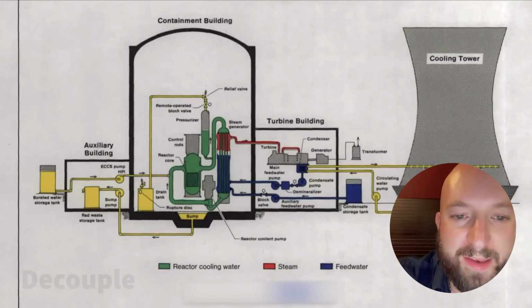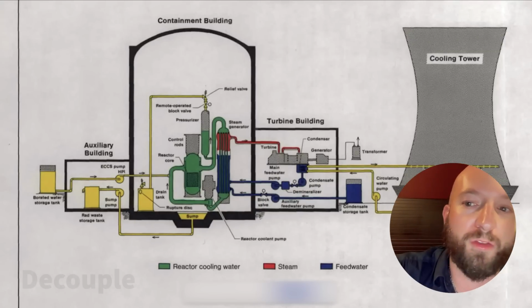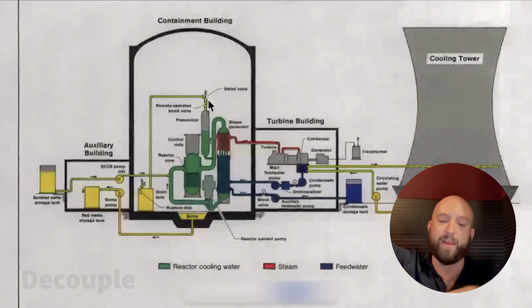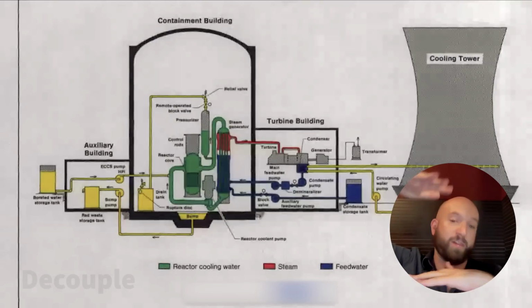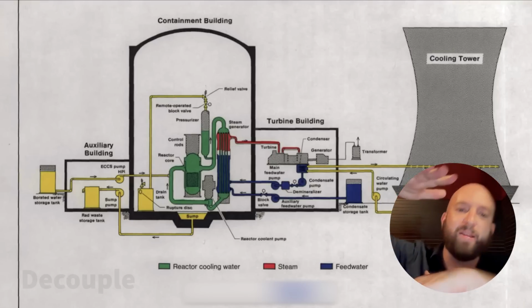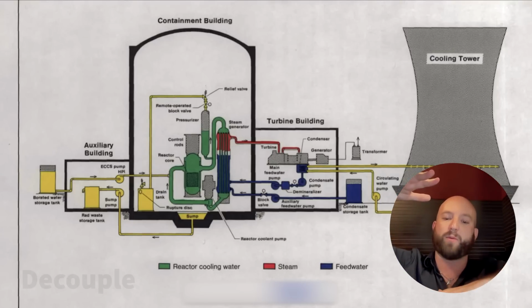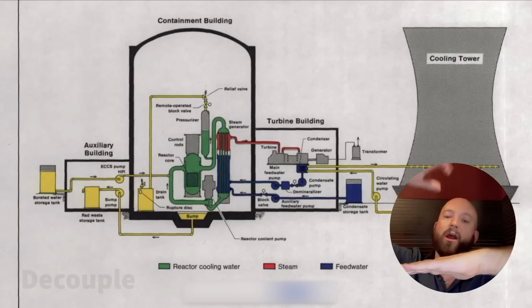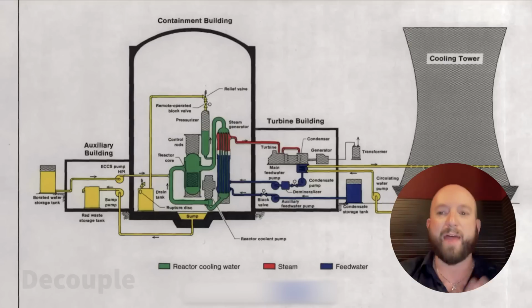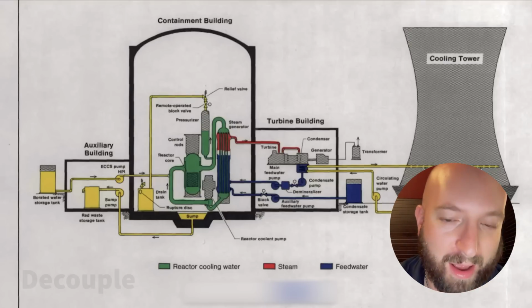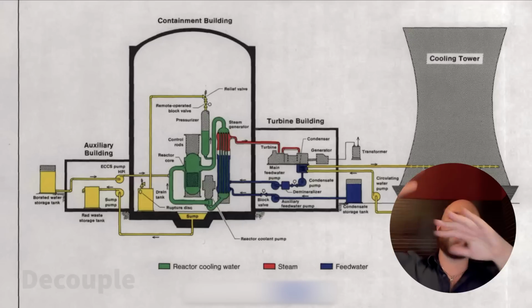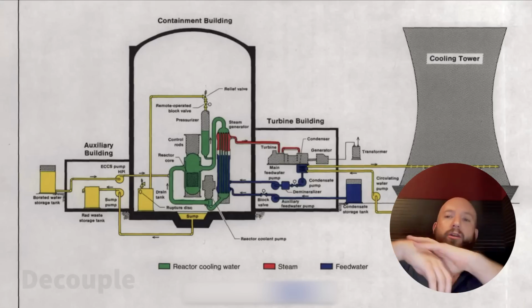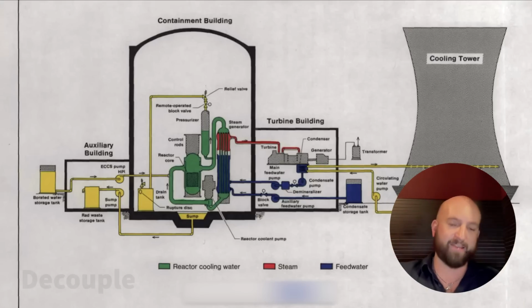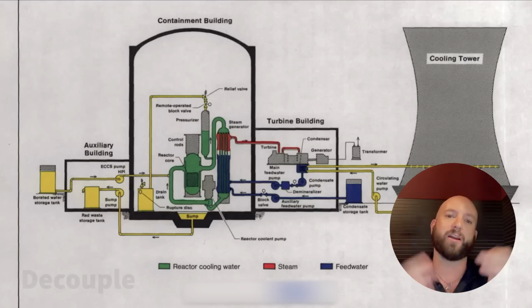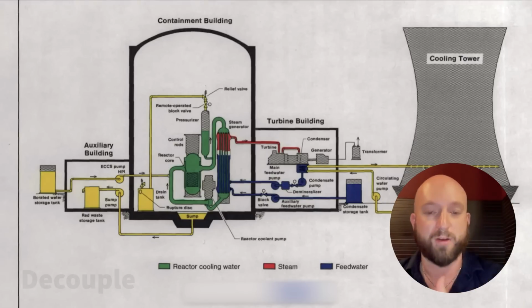What would happen if it didn't open or if you didn't release the pressure? That's a great question. So actually on this, there are the pilot operated relief valves. Then there are what are called the safety relief valves, which are spring loaded valves, or the safeties, you'll hear them called, the SRVs. They basically just open when the mechanical force of the reactor coolant system gets larger than the force of the springs holding them down. And the reason why we don't generally like to have those operate is because the safeties often, when you lower the pressure, don't seat properly. So you don't generally want to have the safeties relieve in any situation. But even if they did, it's a really bad situation because you'll have to generally send someone into containment to reseat those safety valves if they get open.